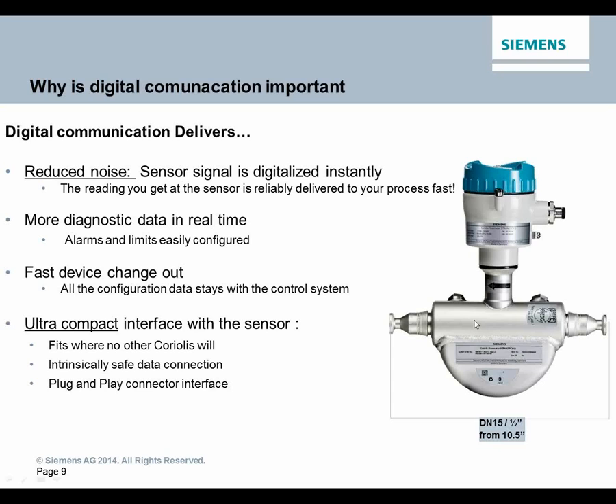In order to combat that, in the design of this meter, let me put my little spotlight back on. This section right here, this is the main support structure. This is our smallest meter pictured. It's a 1/4-inch tube. This section is 304 stainless steel, and it is over 1/4 of an inch thick. So what it was designed for is to take incredible forces from the inlet to the outlet and transfer it directly straight through the case, not affect the tubes that are underneath. So what they have done, in the design of this meter, is mitigated that particular problem. You can never really eliminate it 100%, but that was a great question, and the design of the sensor was designed in order to help deal with that very serious, very particular problem, the Coriolis meter.